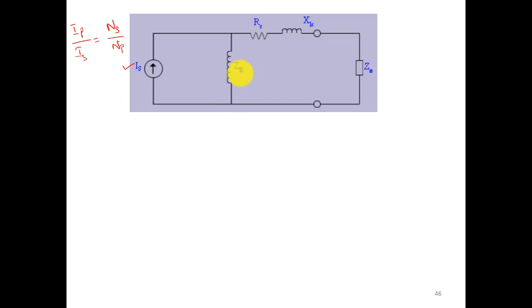This is the final simplified model after transferring the primary side equivalent circuit to the secondary side. The primary current Ip is referred to the secondary side as Is, where Ip/Is = Ns/Np. Ze is the exciting impedance referred to the secondary side. Rs is the secondary side resistance, Xls is the leakage reactance, and Zb is the burden — the relay plus lead wire impedance.